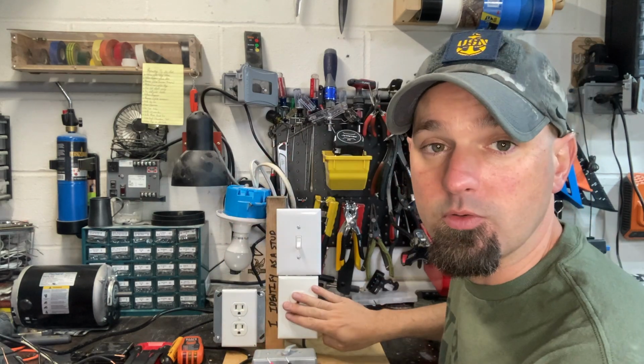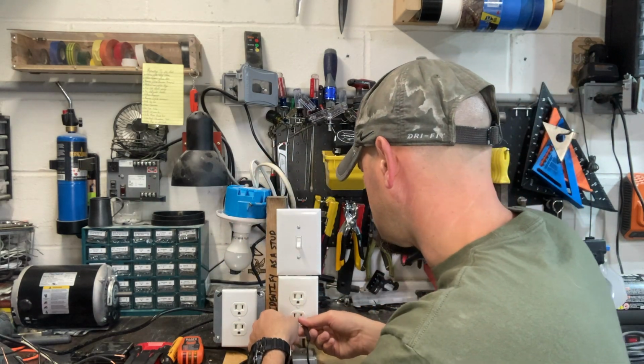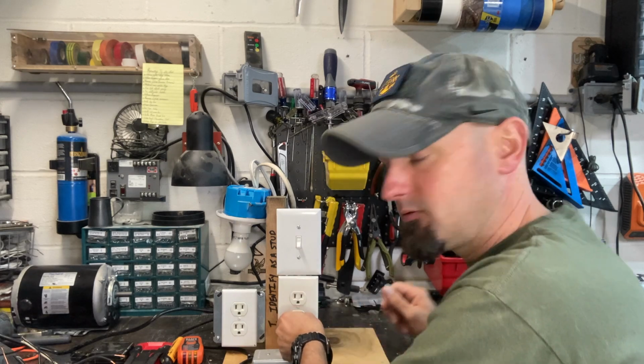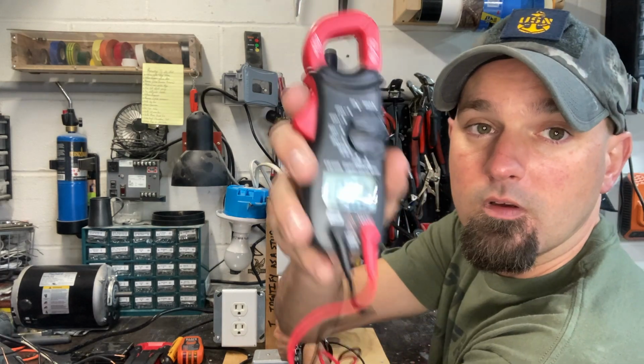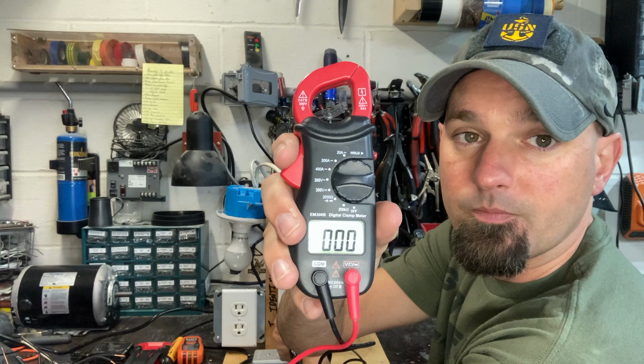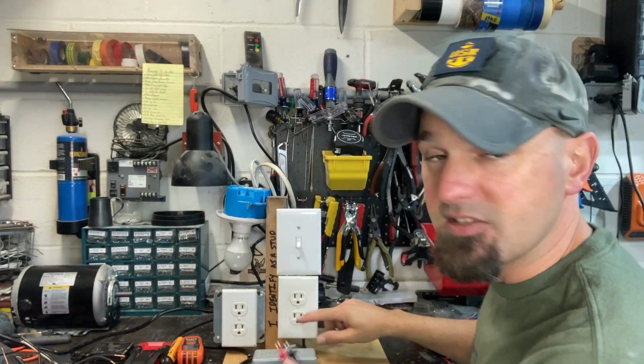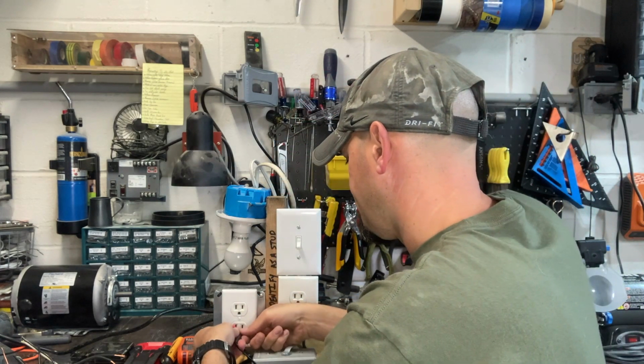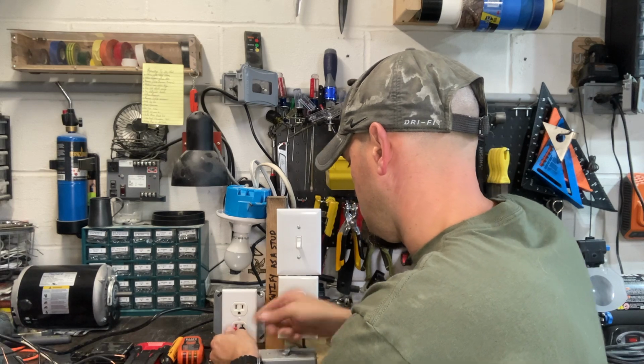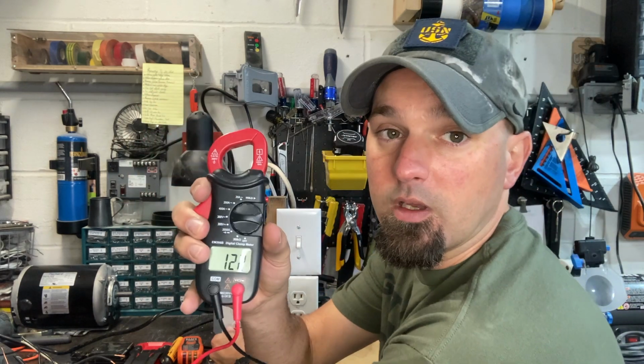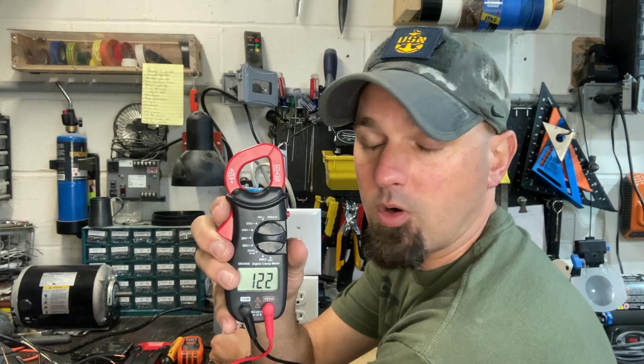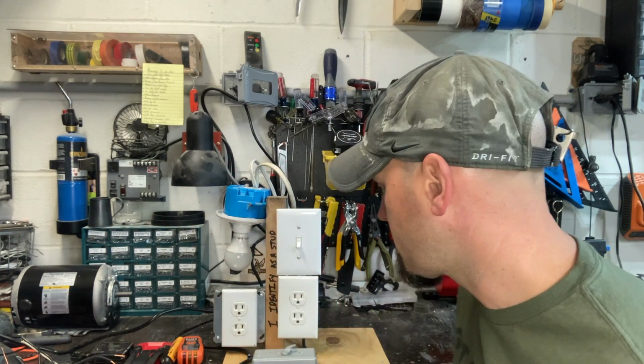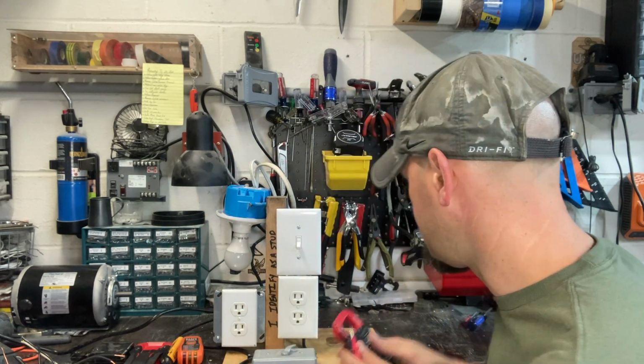Now I'm going to come over to the one I'm going to be working on, and do the same thing. And now it's telling me I've got 0, okay, that's fine. Now we've tested the dead, let's go back to the live - and look at that, I have 122 volts. So I know my meter is properly working, and I know 100% that I've turned this off.